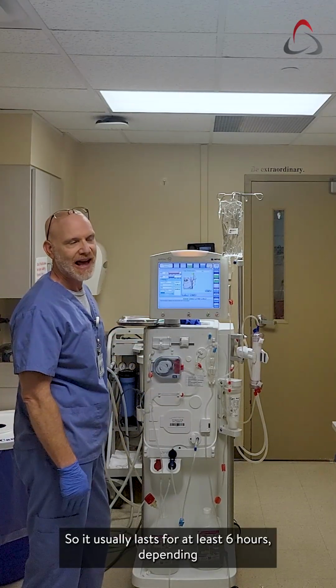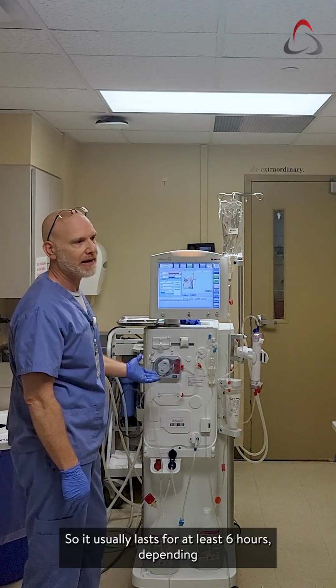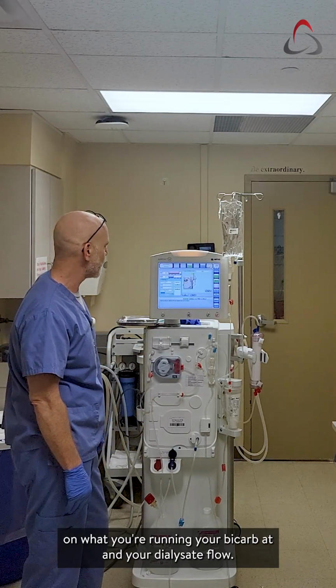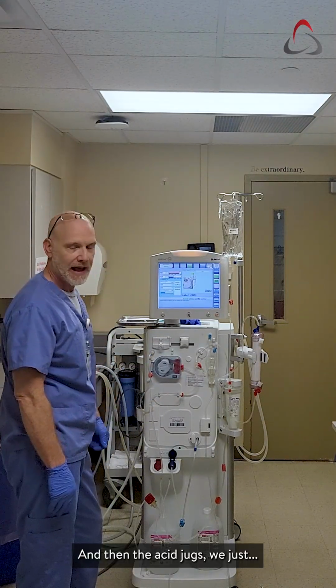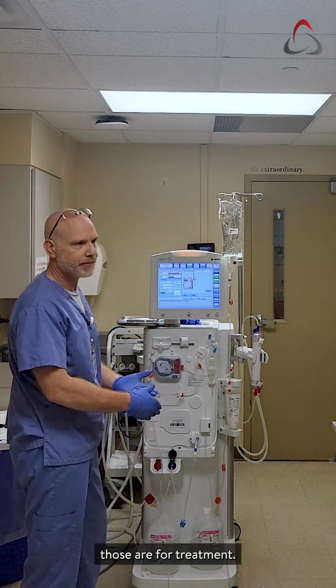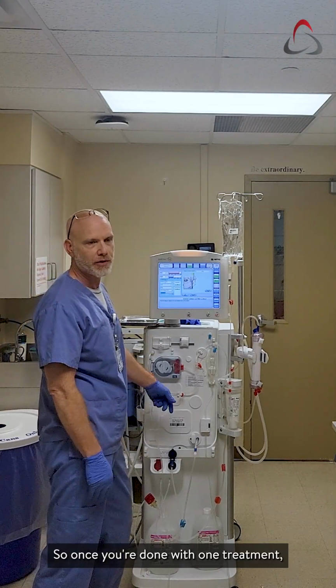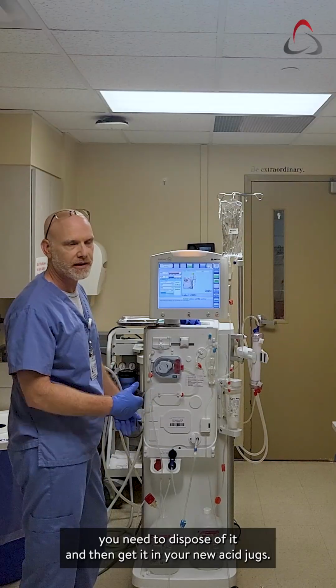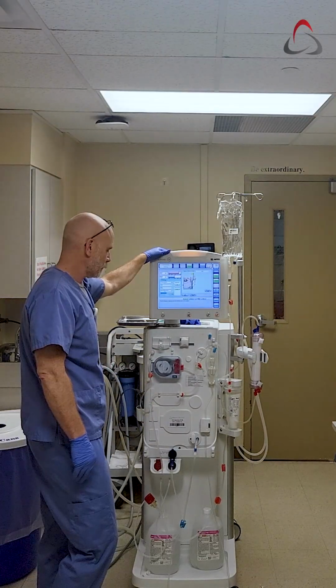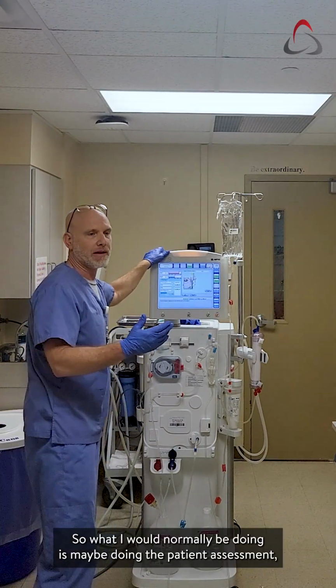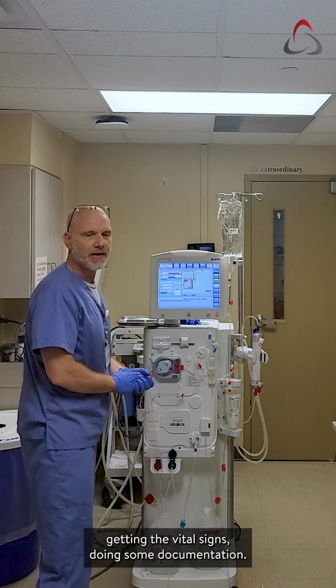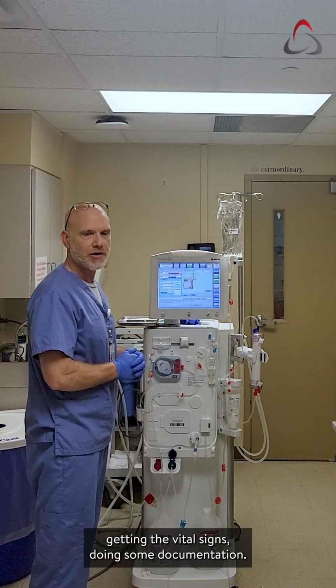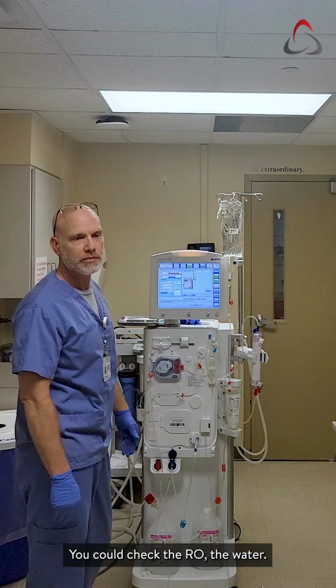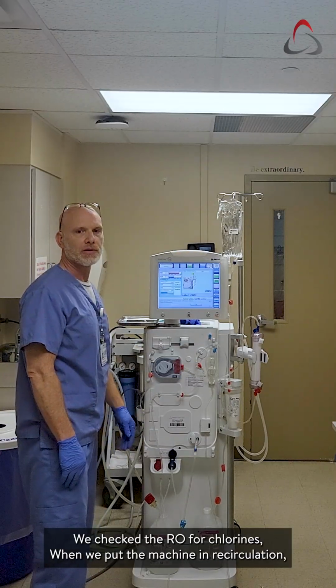So it usually lasts for at least 6 hours, depending on what you're running your bicarb at and your dialysate flow. And then the acid jugs, those are for treatment. So once you're done with one treatment, you need to dispose of it and then get your new acid jugs. So what I would normally be doing is maybe doing a patient assessment, getting the vital signs, doing some documentation. You could check the RO, the water. We check the RO for chloramines.